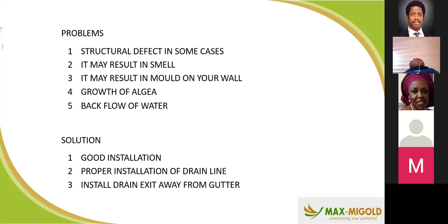Your AC environment must be dry, neat, and properly installed for you to get a good, sound AC working in your facility. Good installation, proper installation of the drain line, then install the drain exit away from gutters. Some drains actually discharge where they smell, so smell can follow through those small holes and be discharged into your space.